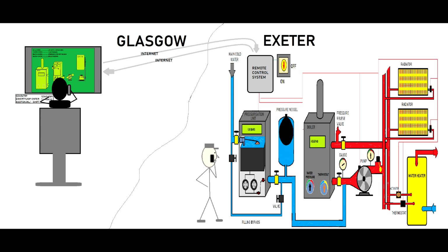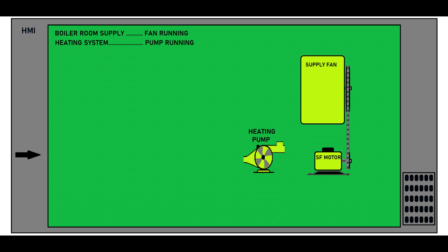But the engineer who went to the premises will call and say, hey, the pump is not running. And they start arguing a little bit on the phone, because the guy from the office will say, hey, the pump is running, I can see it on my computer, everything is okay, so you better try to investigate what's wrong. And the engineer on the spot says, no, the pump is not running, I'm here, I can see it. So how do you see the pump is running when it is not? And there will be this little conflict backwards and forwards. And obviously the engineer in the field is right, because he can see with his eyes.